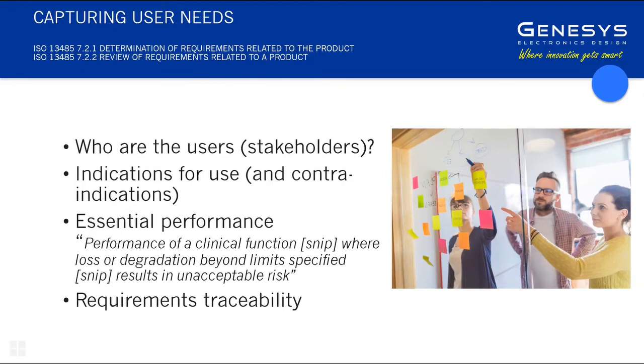One thing I've noticed sometimes with user needs is you can have things that sort of duplicate or overlap each other. Just how important is it to have each user need almost mutually exclusive from each other? It's really important to have them extremely simple and clear cut, preferably in terms of one-liners, not to have thousands of them. If you have more than 100 user needs, you've probably strayed into the territory of what we call design inputs, which are in fact the technical specification parameters. So each user need might give rise to 10 design inputs.